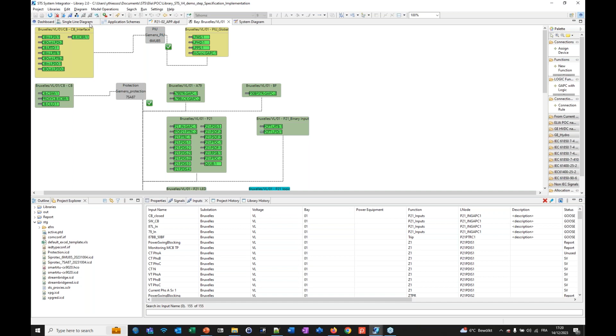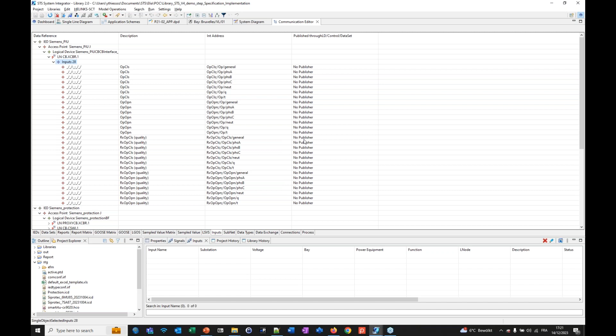Then when we have done all this job, we can generate the communication. Just before that, I will show you the communication editor, where you will see we have two IEDs, the Siemens PIU and protection, but no data set in these IEDs. If I show you the GOOSE matrix, we have no GOOSE message and no subscription to GOOSE. And in the input representation of our SCD file, for example in the PIU, we have 28 XRef predefined, but this subscription is not currently connected to a publisher GOOSE control block.